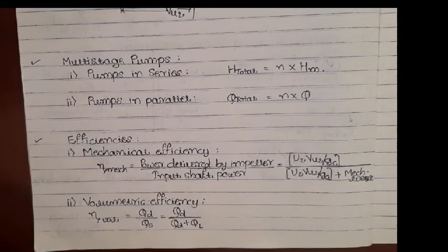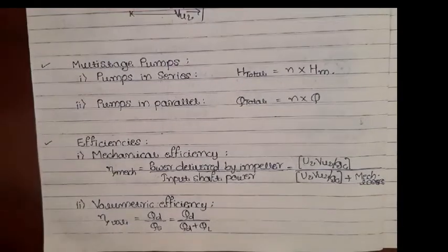In those cases it may not be sufficient or feasible to do the work using only a single pump which is quite large, because a large pump is always costly. Plus, in order to achieve higher discharge I cannot go on increasing the delivery angle. The beta 2 cannot be increased more than 45 degree, which will decrease the total efficiency.